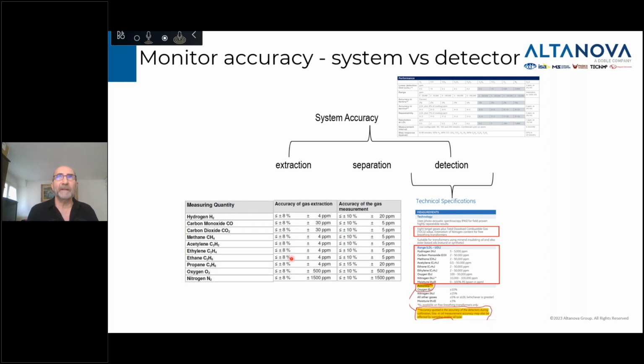So right at the beginning, you're outside the IEC spec, and it tells you that whatever comes out of that specific equipment, the measurement is not going to be highly accurate. And also you have to do the same thing on the LDL. What you see here is that for the majority of the gas, the LDL is around 9 ppm, and for the hydrogen it is 24 ppm. So again, when you have that kind of spec and you're comparing to someone else's spec, you have to add all those accuracy numbers and the LDL number.